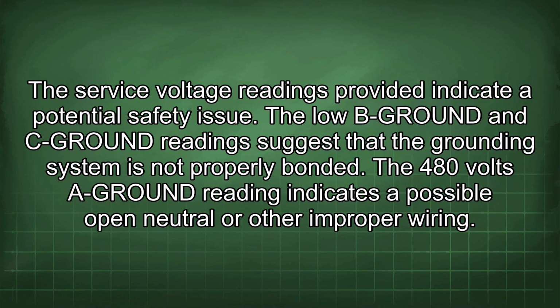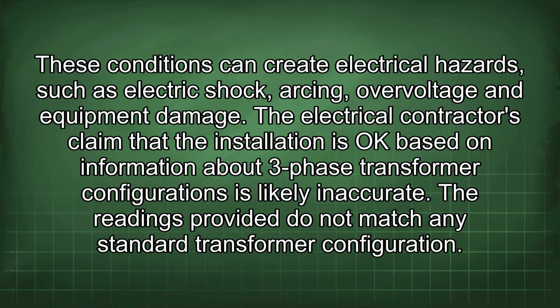The service voltage readings provided indicate a potential safety issue. The low B ground and C ground readings suggest that the grounding system is not properly bonded. The 480 volts A-GROUND reading indicates a possible open neutral or other improper wiring. These conditions can create electrical hazards such as electric shock, arcing, overvoltage and equipment damage.